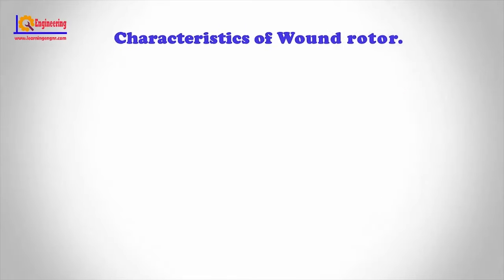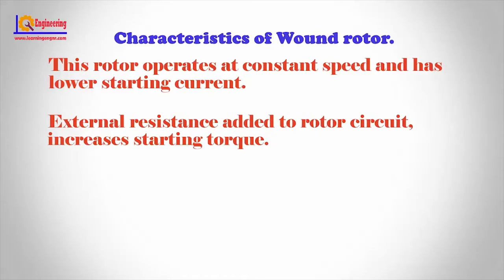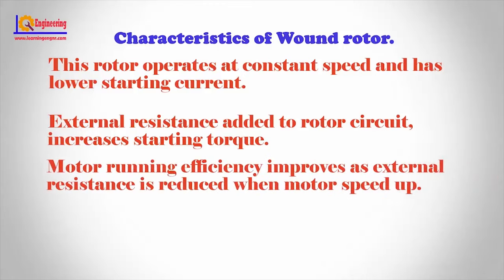Characteristics of wound rotor: This rotor operates at constant speed and has lower starting current. External resistance added to the rotor circuit increases starting torque. Motor running efficiency improves as external resistance is reduced when the motor speeds up. It provides higher torque and speed control.